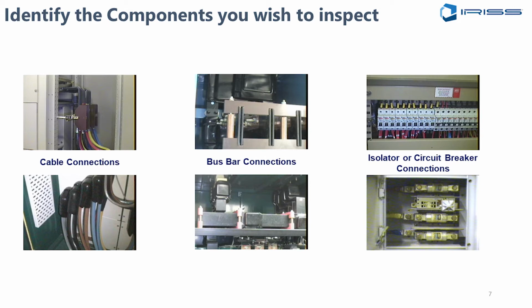Now, what is it that we want to inspect? I usually tell people that the primary points of failure in electrical apparatus are where we transition from one conductor type to another, where we go from cable to bus, where we have a lug or a crimped connection. All of these suffer from the same potential phenomenon: two dissimilar metals will have different coefficients of thermal expansion.